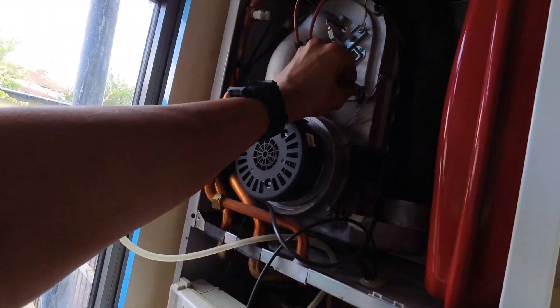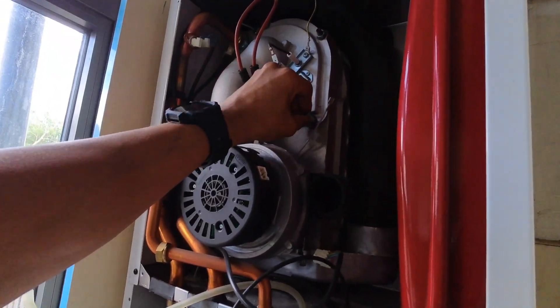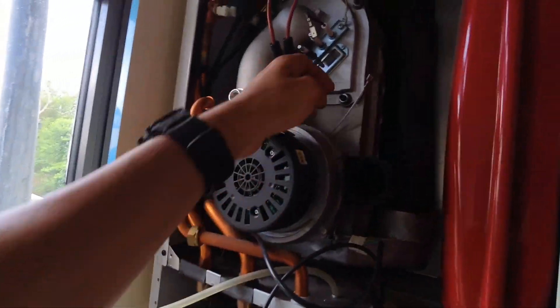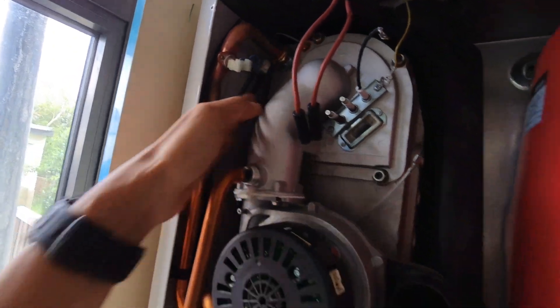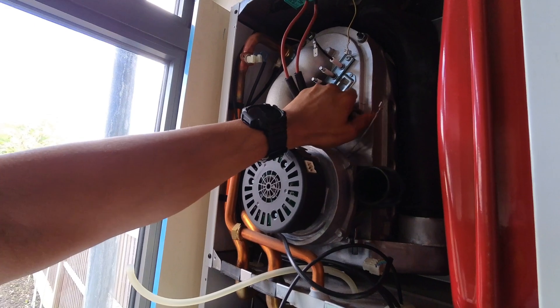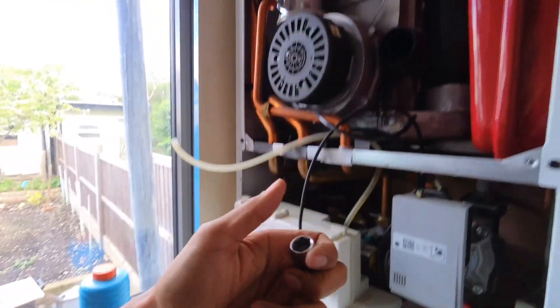This is a little bit concerning — I was pretty sure it's a 13mm socket for these nuts, but when I put it on it's moving loosely. I thought maybe I got it wrong — maybe it's a 10mm, but 10mm is too small. Got a 12mm out — that's too small too. Then I realised that nut hasn't even been tightened up properly, it's only been hand-tight. I wonder if any of the others are the same. The others seem okay, but yeah that one was only hand-tight. Let's get them all off — replacing the burner gasket, the electrodes, and so on.